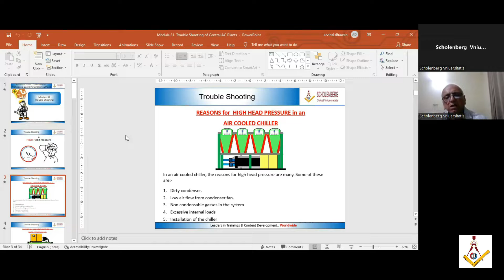Next is excessive internal loads. Suppose the internal loads have increased, occupancy has increased, or some equipment load has increased. And next is installation of the chiller. Now, suppose you have installed this air-cooled chiller in open direct sunlight, it will affect it, right? So environment also plays a very important part in the head pressure of the plant. That question was for high head pressure. When you've opened the module, you can go through all this.